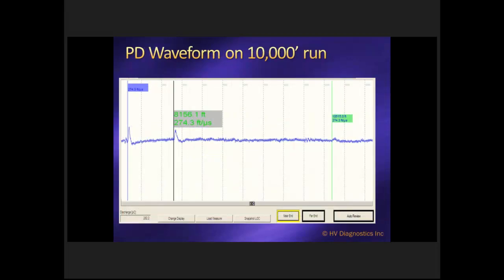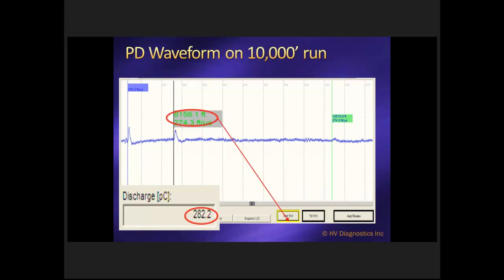Then we do the PD measurements, and as you can see over here, we see a PD signature coming back from 8,156 feet from the far end, so it's actually pretty close to us. And you can see the impulse, the picocoulomb value of the PD, in this case 200 picocoulombs, so relatively it's big enough to be damaging to the cable, but obviously less than what we injected during calibration. We have another one at 8,981 feet. You remember the previous one was 8,156 feet. So what we've got here is actually two PD sites in the same cable. It's quite an interesting situation we found ourselves in. And this particular PD impulse is 437 picocoulombs in amplitude.